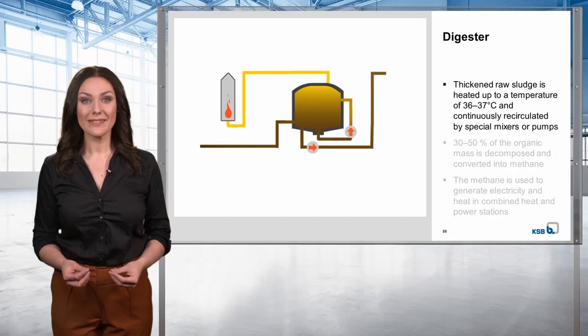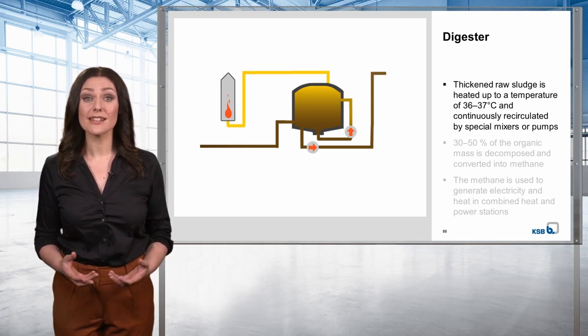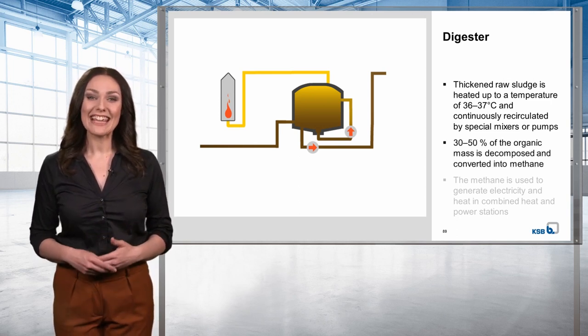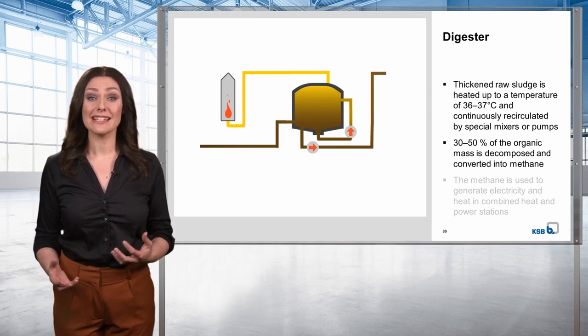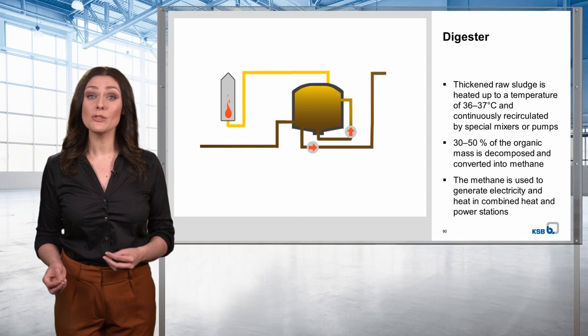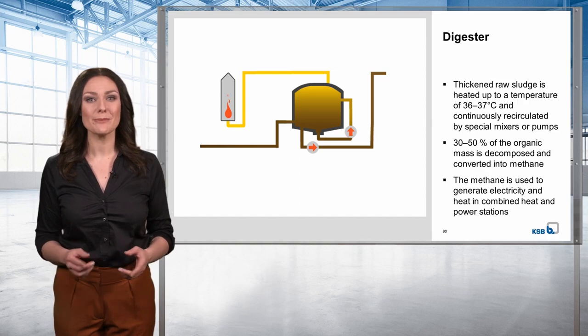Large wastewater treatment plants are equipped with a digestion tank in addition. In the digestion tank, already thickened raw sludge is heated up to a temperature of 36 to 37 degrees Celsius and continuously recirculated by special mixers or pumps. In the digestion process, part of the organic mass — approximately 30 to 50 percent — is decomposed and converted into methane. The gas produced is then used to generate electricity and heat in combined heat and power stations for the wastewater treatment plant. After the digestion process, the so-called digested sludge is removed from the tank and thickened once again, and is then usually burned.